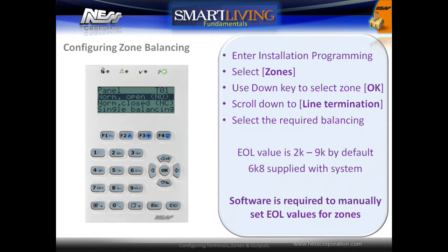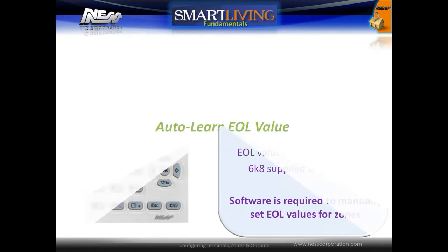To configure zone balancing, enter into installation programming, scroll down to Zones, use the down key to select the zone to program, and press OK. Scroll down and select Line Termination, then select the required balancing. The system will automatically recognize a 2k to 9k end-of-line resistor value. 6k8 is supplied with the system. Using the software, individual end-of-line resistor values can be programmed per zone if required.